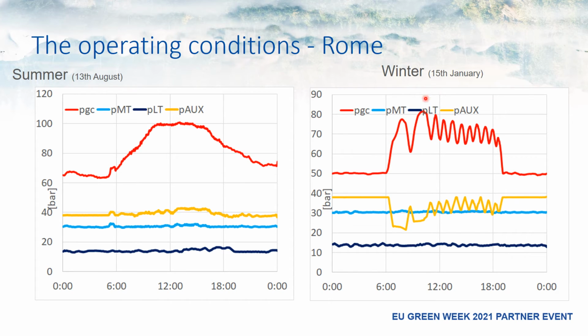On the right-hand side, winter operations, you can see that the air handling unit heating mode is switched on during the day, and in this situation the gas cooler pressure is increased to recover heat and to heat up the supermarket. And here we can also see the suction of the auxiliary compressors, which are working as a heat pump in the heat pump functionality, and so the evaporation pressure of the outdoor evaporator depends on the outdoor temperature. Here we have the average values, the maximum and minimum values in the summer and in the winter.